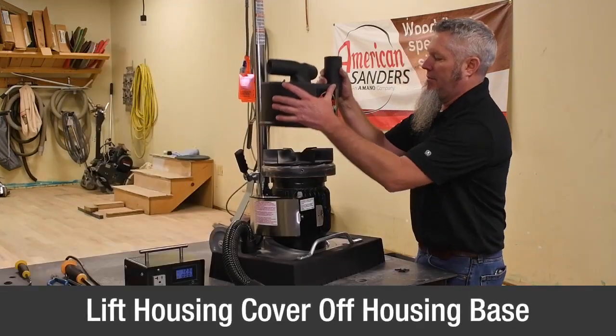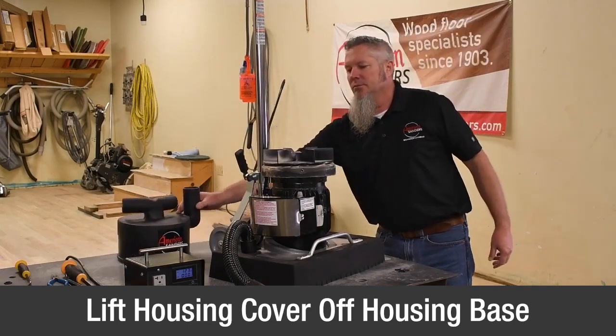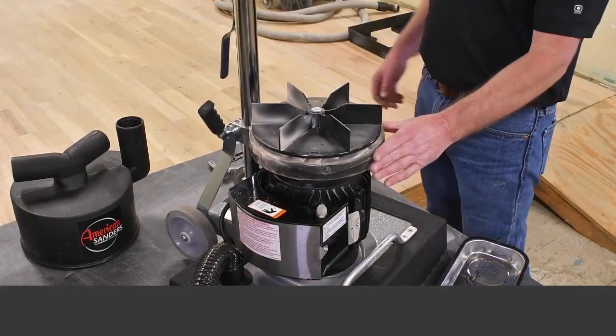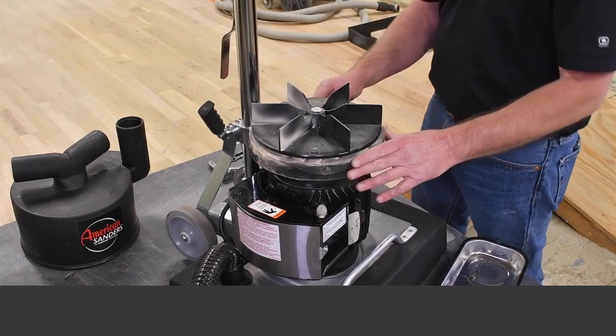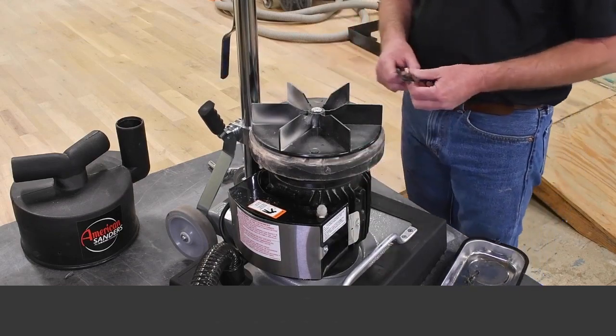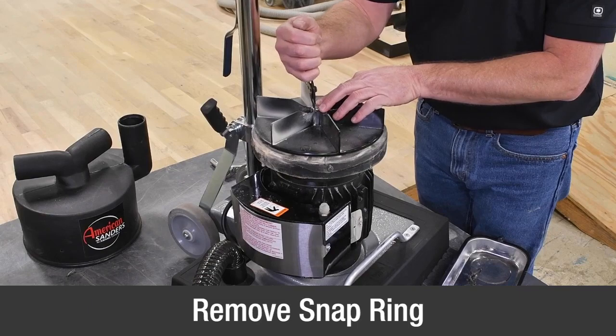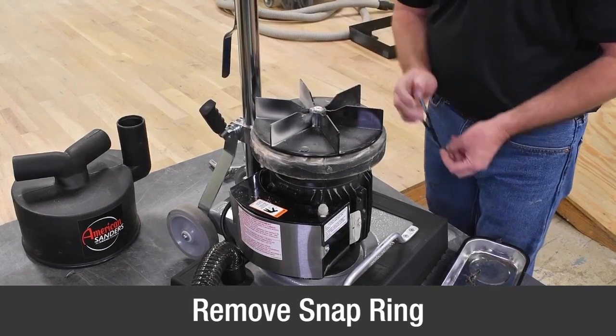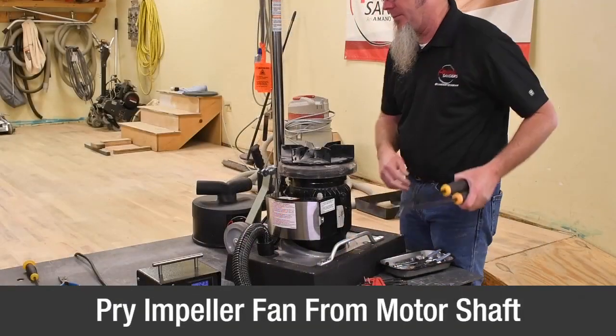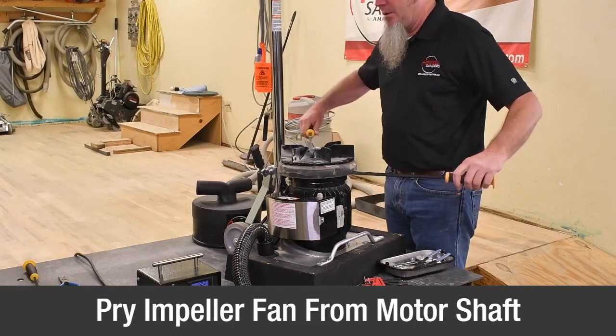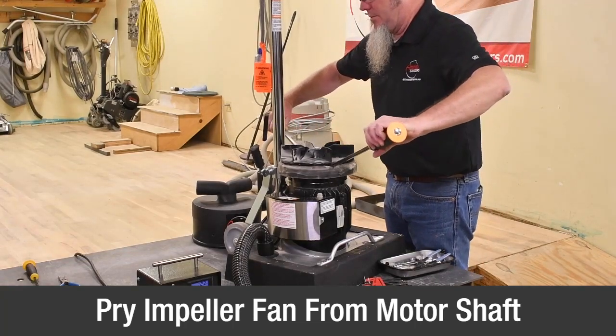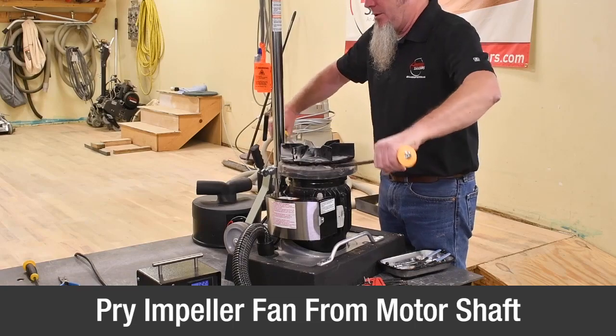Then lift the blower housing cover off the base. Remove the impeller from the housing base with these steps. Remove the snap ring. Use 2 equal-sized pry bars to lift the impeller off the shaft. Place the pry bars on opposite sides positioned underneath the fin.